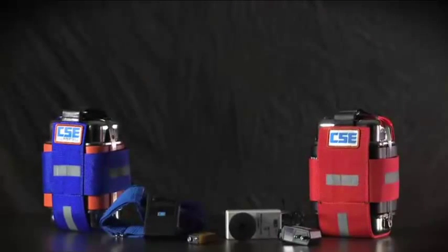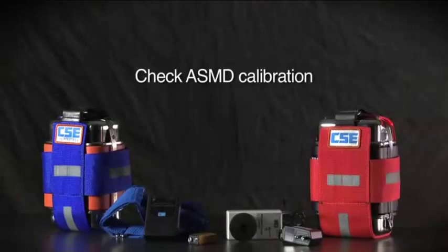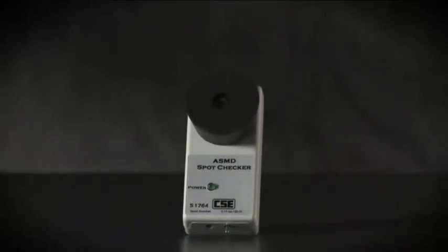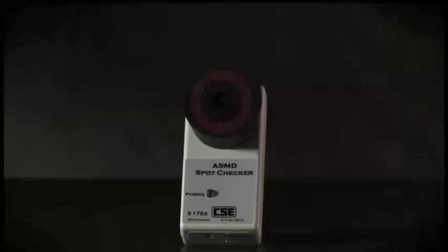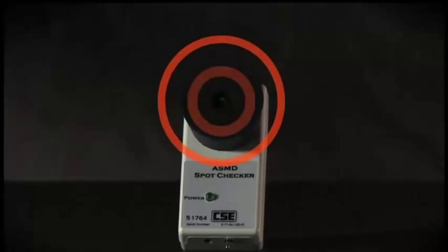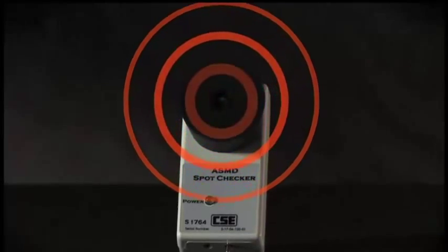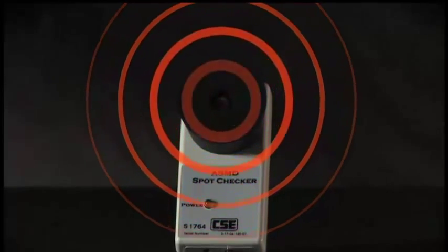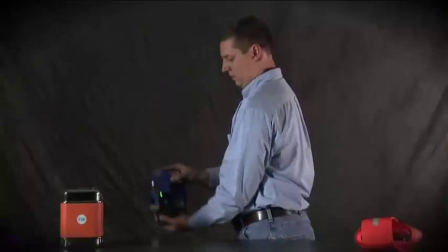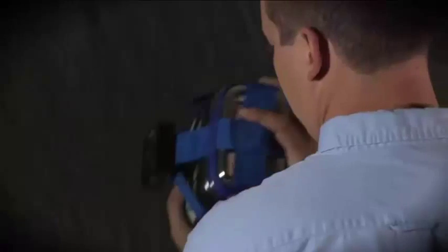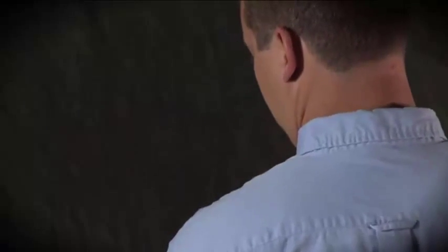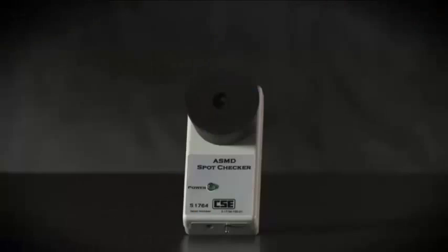At the start of every testing day, check the ASMD's calibration using the CSE spot checker. The calibration check is a simple procedure, but you should schedule enough time to do it carefully. The spot checker duplicates the abnormal sounds that the ASMD is designed to detect. If the spot checker sets off the ASMD's red failure light, you will know that the ASMD's sensitivity is set correctly. First, check the calibration date sticker.